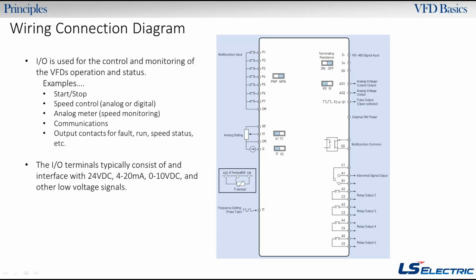We also have all of our outputs on the I/O. That's what the O stands for. You have these relay outputs on this one. These could go open or close based on certain conditions. Sometimes you'll hear a person say, hey, I need a run status. What they would do is wire up to A2 and C2, and that will be a contact closure whenever you're running, and then it'll open up whenever you're stopped. You could use that for a light. These are all meant to interface with other devices, whether it's a switch or a push button on P1 through P7, a speed pot or some kind of controller on the analogs, a communication network, or relay outputs going to buzzers or lights or other things in a process. You could have the drive start up and then have another thing down the line start up. So that's what all the I/O is.